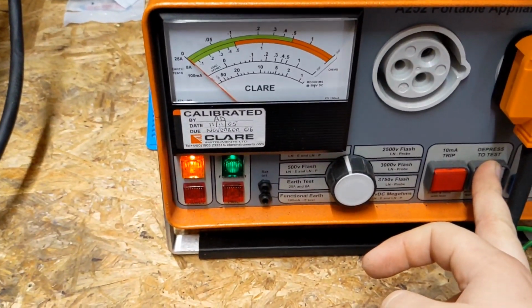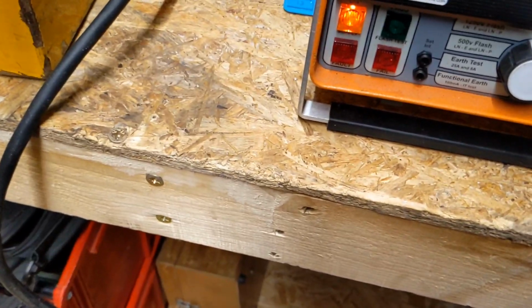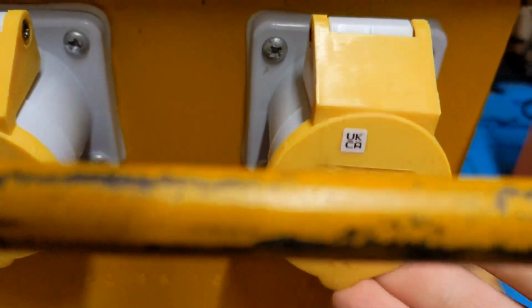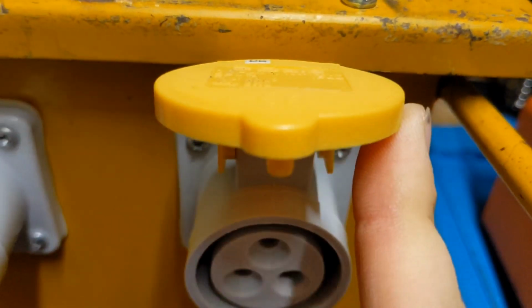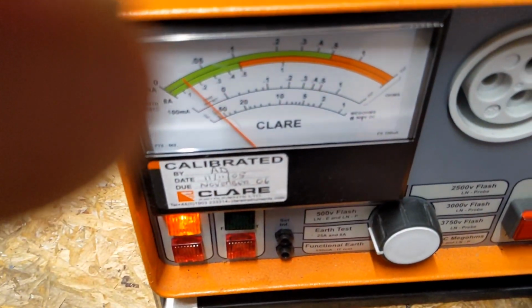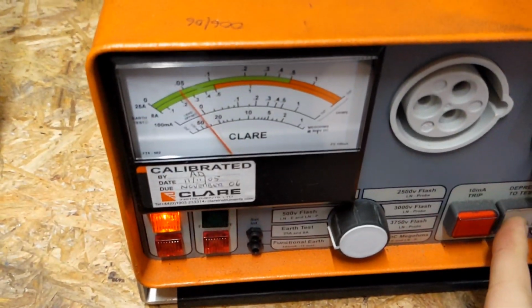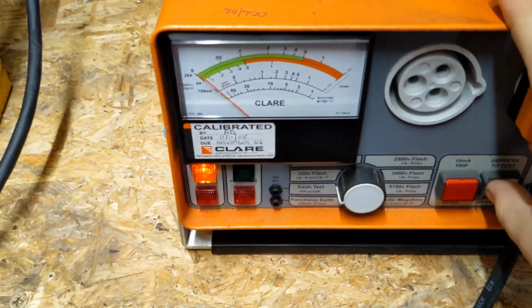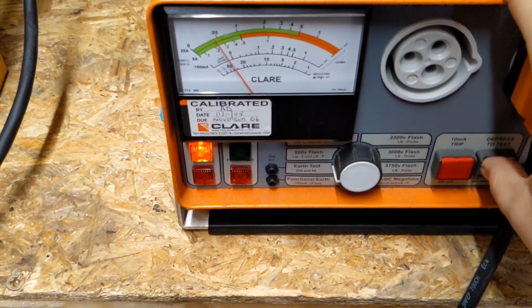I'm doing a quick flash test - green light. What we're going to do now is quickly make sure that the socket earth is there as well. They fit new sockets, so we've got a test probe and we'll stick the probe in. Yes, earth is good on that socket. I'll check the other one - yeah, the earth is good on that socket as well.